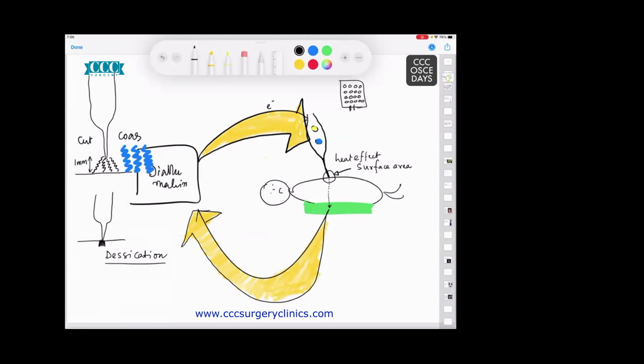And if you want a coagulation, say for example, there is a raw surface and you need a coagulation, please hold it 2 millimeters away and see the beauty about this lightning. This is how the principle works. And if you have known about this, I feel that you have known what the local complication is. The local complication is usually a heat effect or burn.